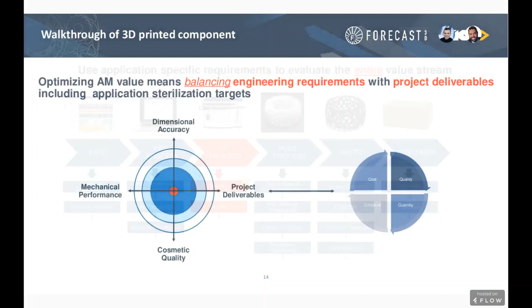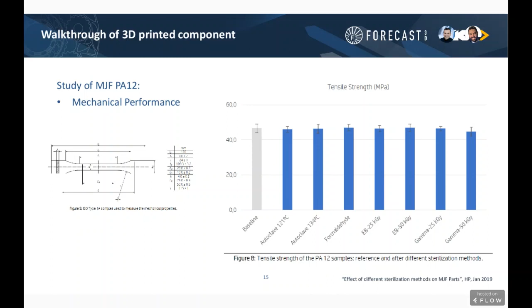So depending on what method you're going through, the results will change, and you can see how they change from the baseline here. On average, the tensile strength remained fairly similar for their PA12 product. If we go to the next one, it's evaluating the elongation at break. You see a little bit more variation with what the processes are doing to the base material. And this is just here to help you understand if this material and this technology will be a fit for you. The next slide shows a slightly different version, where it's the tensile modulus and how the sterilization process affects those results.